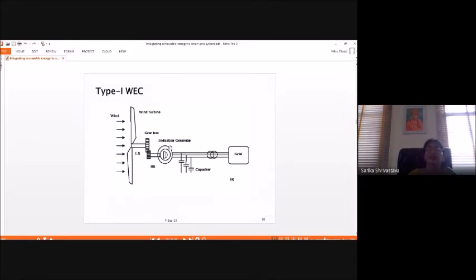Induction generators are three-phase generators, and initially they work as a motor. They draw power from the electrical grid to start as a motor, and when the speed becomes sufficiently higher than the synchronous speed, the direction of power flow reverses and it acts as a generator. Then this power is fed to the grid. As we discussed earlier, reactive power is required to start the generator. But if we take the reactive power from the grid, it will destabilize the grid. So to meet reactive power demands, local capacitor banks are there which can fulfill the local demand.